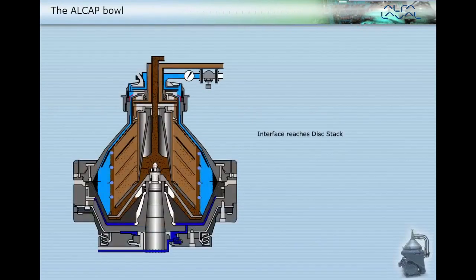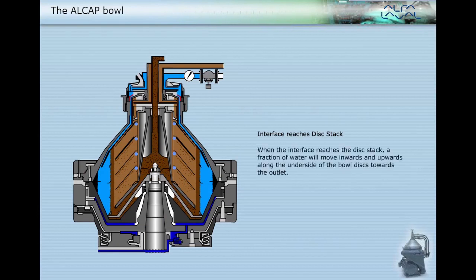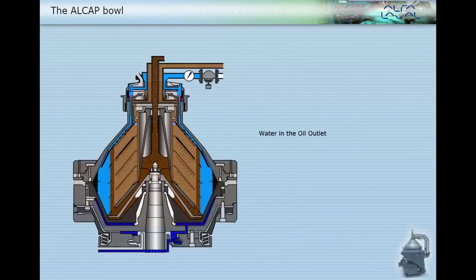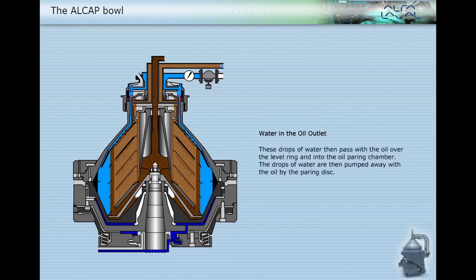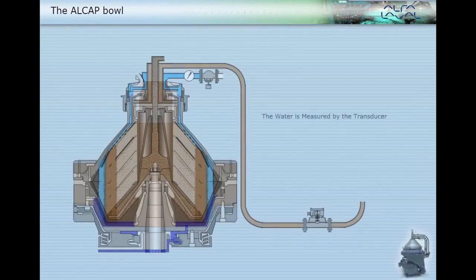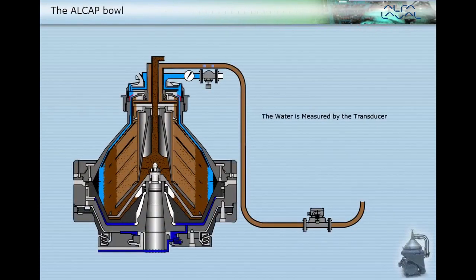When the interface reaches the disc stack, a fraction of water will move inwards and upwards along the underside of the bowl discs towards the outlet. These drops of water then pass with the oil over the level ring and into the oil paring chamber. The drops of water are then pumped away with the oil by the paring disc. This changes the overall dielectric constant and will cause a change in capacitance reading.